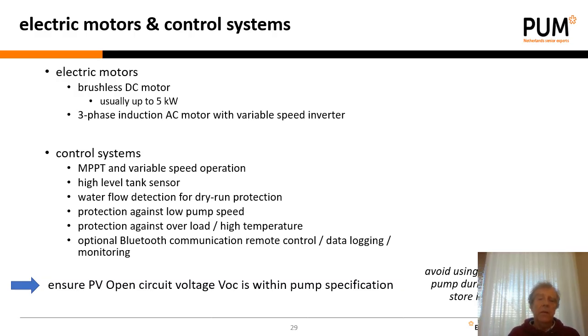Then, if we look at control systems, we prefer an MPPT control system which has a better output, and we want variable speed operation because you want to optimize the flow for the purpose that we have. And you would need a high-level tank sensor, for instance, to stop the pumping when the high-level tank is full. Also, you want water flow detection for a dry run protection. The engine could get too warm and it could be damaged.